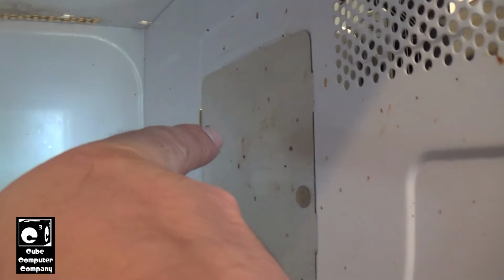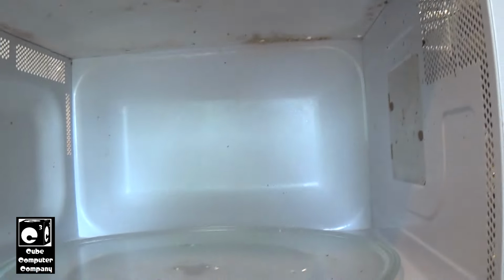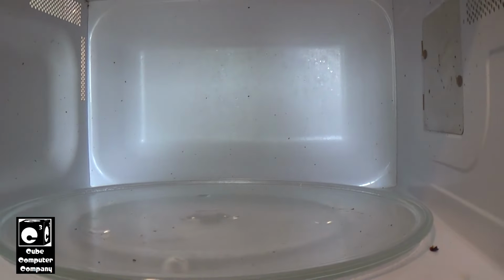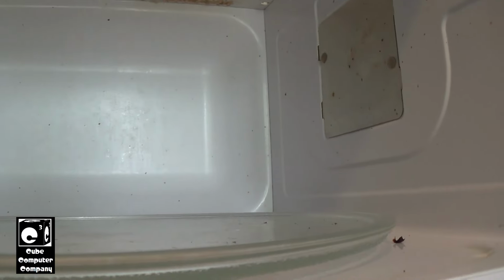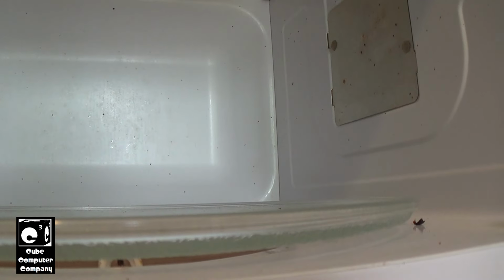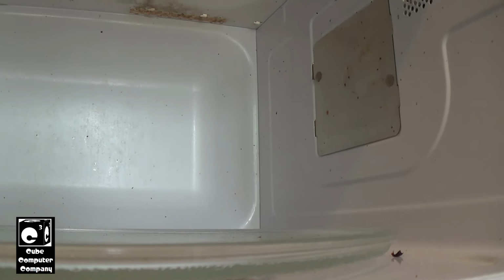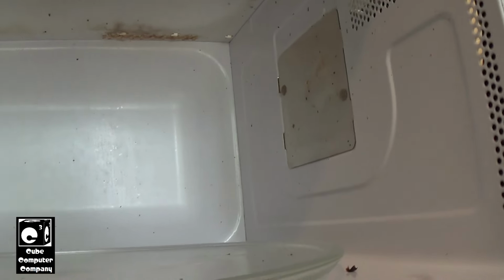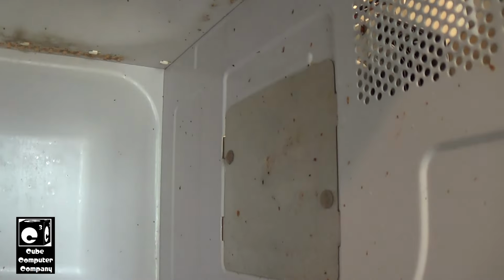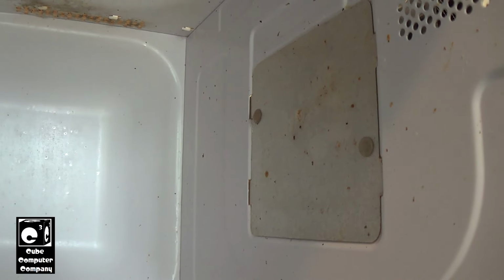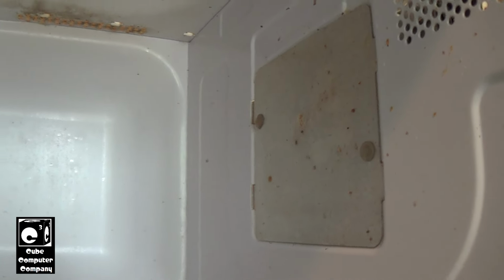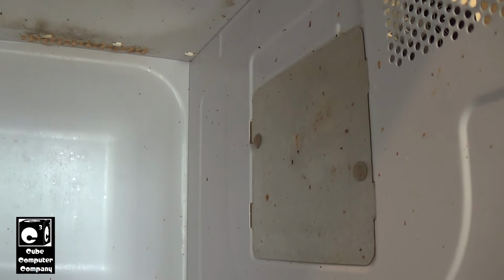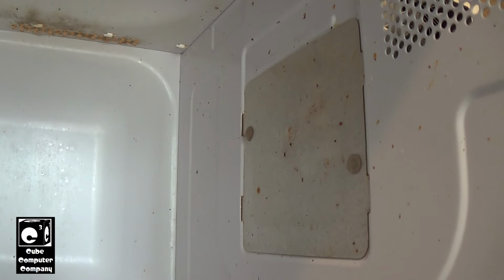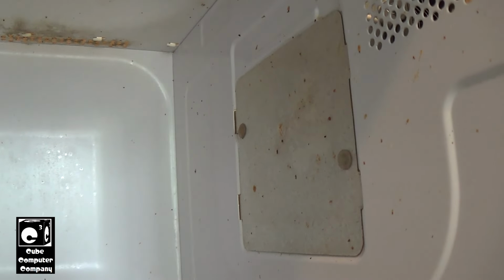So the magnetron tube is inside here, and what can happen is, let's say, for example, the microwave runs with nothing in it. That microwave energy has nowhere to go. I was thinking, okay, maybe somebody was running the microwave with nothing in it, which I doubt. Most people are smart enough not to do that. But, I mean, some people may not realize why you should not run a microwave when there's nothing inside. That microwave energy has nowhere to go, and it ends up going back to the microwave itself.